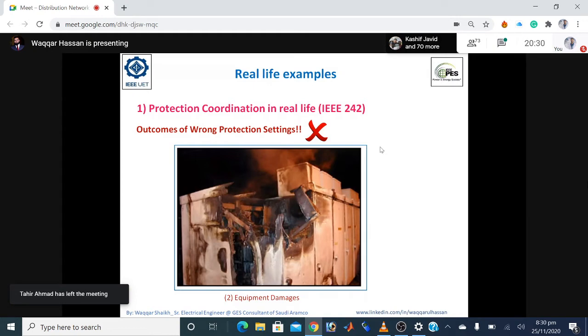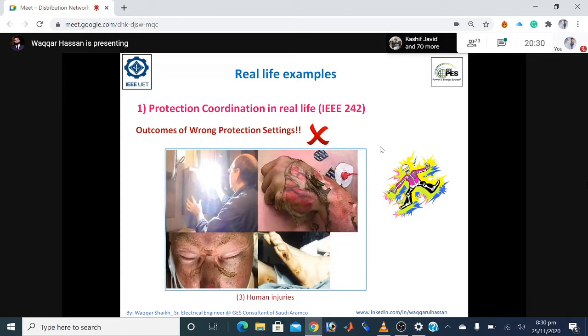And the third and the most important and the most dangerous outcome of wrong protection settings can be injury to human life, and it can even be fatal, up to death. Okay, so if the protection device does not operate at the right time, because of the damage to the equipment, ultimately the operator who is working near that equipment will get severe injuries or second degree burns or even come near to death. Okay, so these are the three outcomes if we are not doing these studies or these protection settings properly. And the international standard which is guiding us for conducting these studies is IEEE 242. It is also called the Buff Book. I will be discussing more about the international standards in the coming slides.